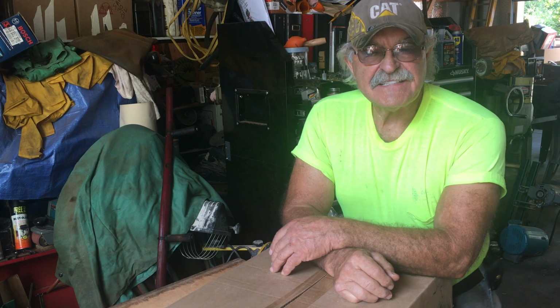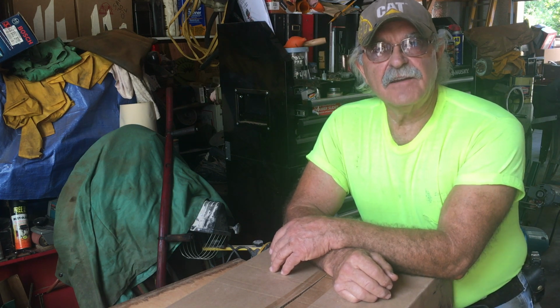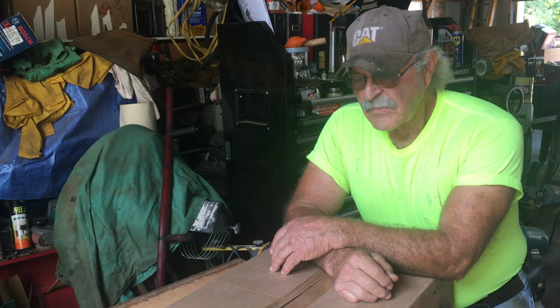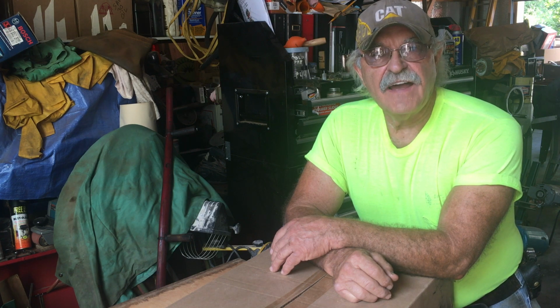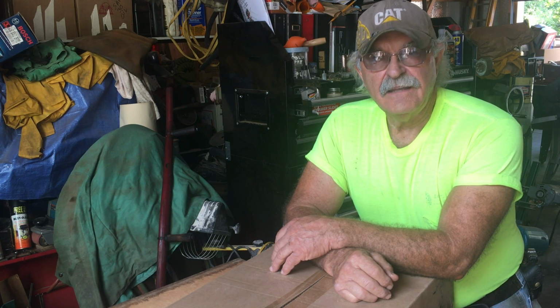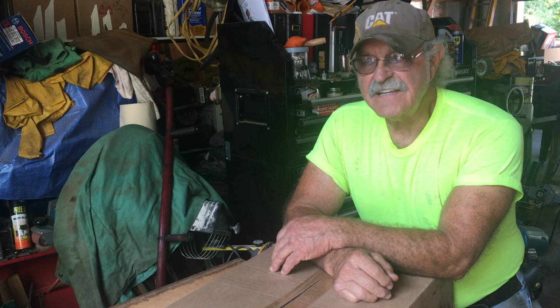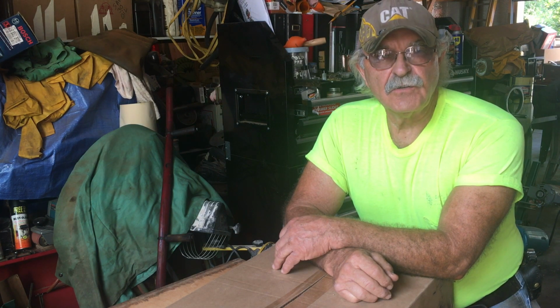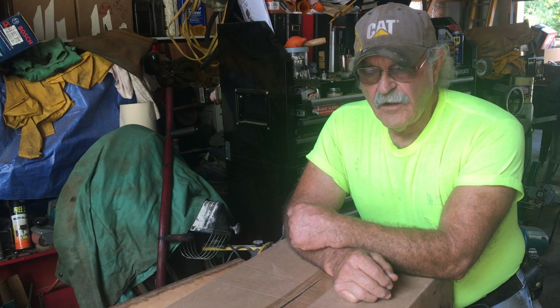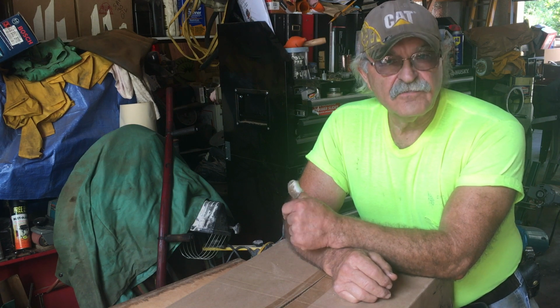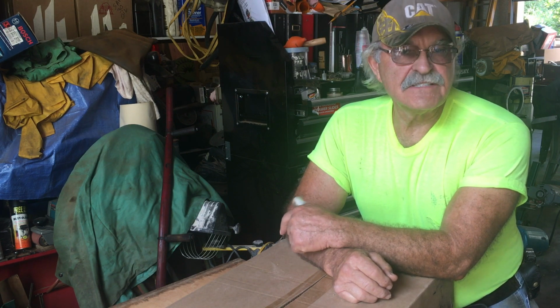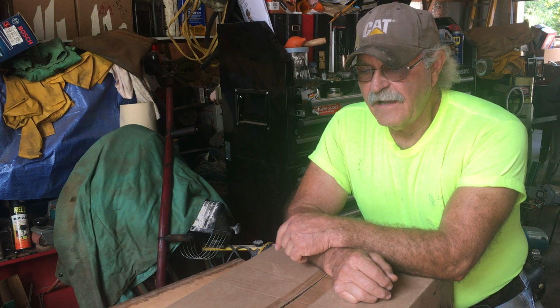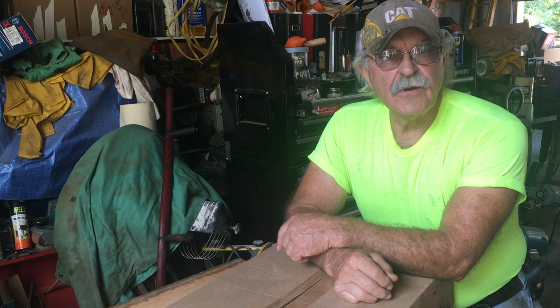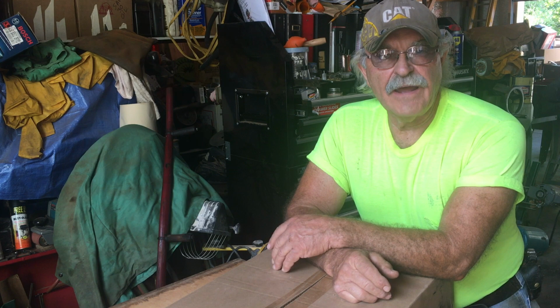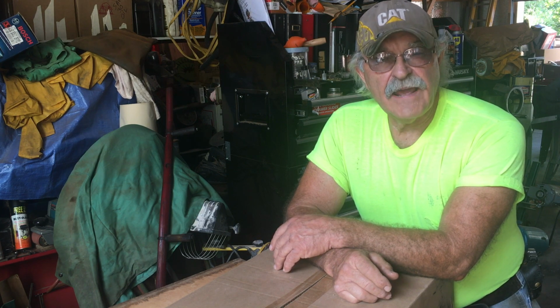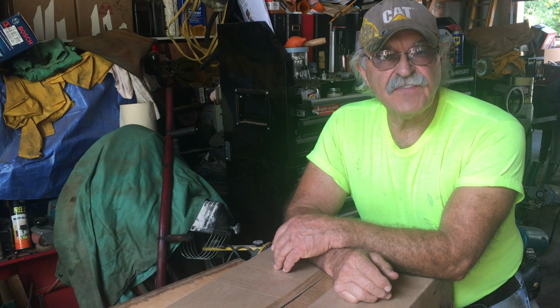He's got a situation where he needs a little more heat down in the basement off of his wood-fired boiler. The upstairs does just fine, there's a hot water coil in the plenum of the furnace that satisfies his house, but downstairs is a little cool. So we came up with the idea of putting a little fan coil in the basement between his pair of studs, with about a 350 CFM fan, to blow some heat into that downstairs family area.